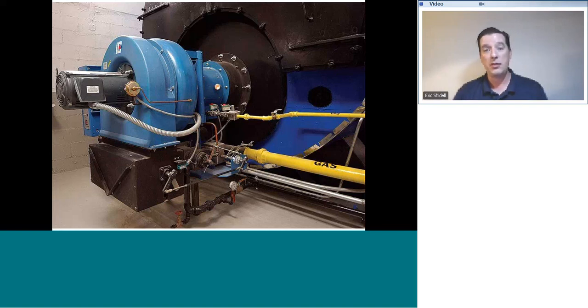So generally, bottom line, if you don't have specific training on these burners, number one, don't mess with them. There's no harm in turning yourself right back around and leaving and saying, I'm sorry, I'm not qualified for this, because you're not. And that's okay. Look at the size of that gas line and imagine how many millions of BTUs, how many thousands of cubic feet of gas are going to dump out of that thing, and realize that an error made in working on one of these burners can have disastrous effects, like the building won't be there tomorrow effects.